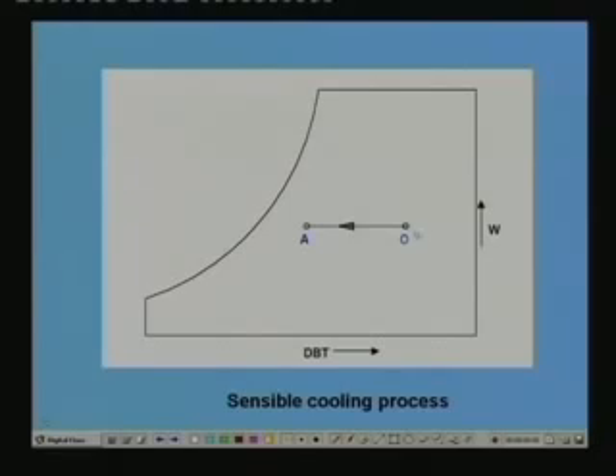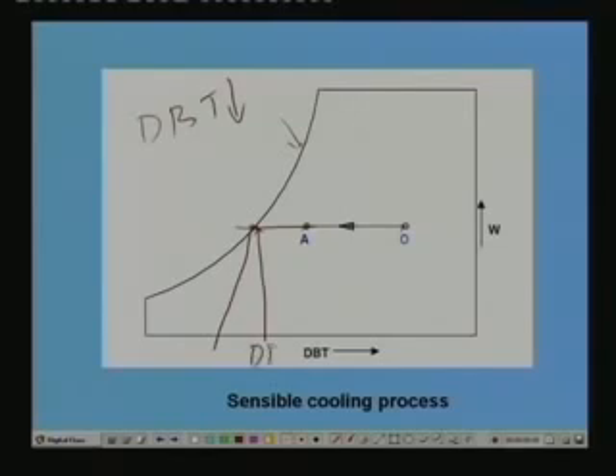Okay. Now, let us see what is happening during this process. As I said, the dry bulb temperature is reducing. Okay. Dry bulb temperature reduces, dew point temperature remains constant, because corresponding to this point or this point, the dew point temperature is this temperature. That means you have to extend this line, and where this line intersects the saturation curve, that temperature will give you the dew point temperature. Okay. So, this is your dew point temperature. Dew point temperature remains constant because moisture is neither added nor removed. Okay. So, DPT remains constant.